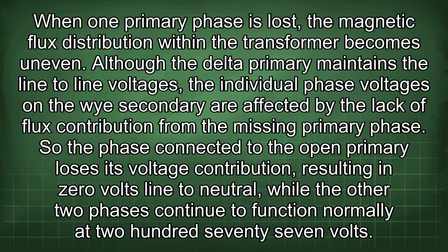When one primary phase is lost, the magnetic flux distribution within the transformer becomes uneven. Although the delta primary maintains the line-to-line voltages, the individual phase voltages on the Y secondary are affected by the lack of flux contribution from the missing primary phase. So the phase connected to the open primary loses its voltage contribution, resulting in 0 volts line to neutral, while the other two phases continue to function normally at 277 volts.